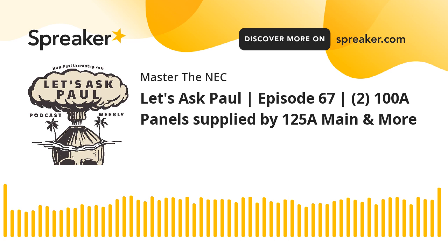Okay, so in that scenario, what we're assuming is that, again, in this panel, you have multiple breakers, and if you start adding them all up, people would get concerned, right? They would think, okay, 70 plus 70 plus 60 is 200. Knowing that there's probably other branch breakers in there, 20 amps or 15s or whatnot, we don't size the service typically by just adding up the devices in there, okay? It's all based on a load calculation. Part 3 or Part 4 of Article 220, it assumes that we do some load calcs here. We have to assume that. Now, the reality is people don't, but they just pick a large one and just go with it. But we have to assume that's what's taking place, right?